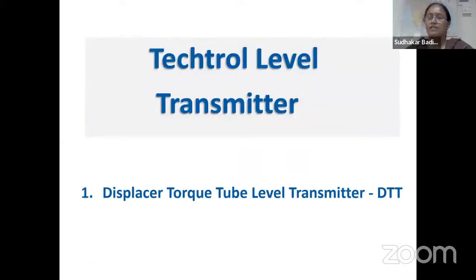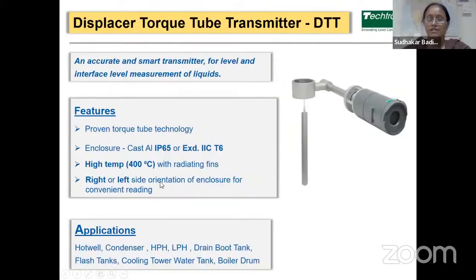Now, these are the level transmitters. This is a displacer torque tube level transmitter. This is an accurate and smart transmitter for level and interface level measurement of liquids. Basically, this is a proven torque tube technology, and it is available with enclosure of IP65 or Exd IIC protection.